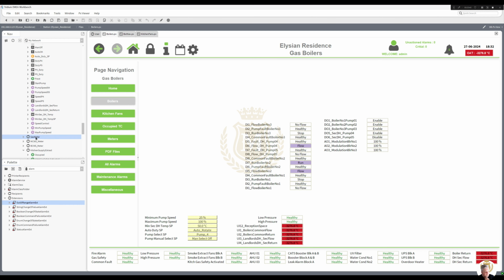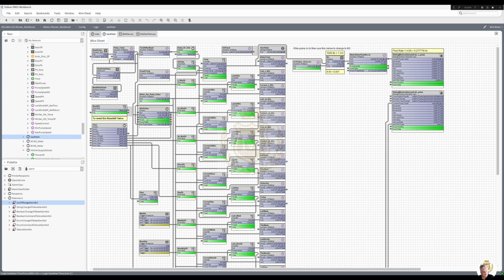What else? Oh, gas meters and MCWS and BCWS. Same folder, same logic in there. You might have seen this before on previous jobs. I have a standard folder that I have with all my bits and pieces in. And we're basically just adding up. So I've improved it since the last time. I've put the meter pulse value in. At the moment I always had it as a 1, but now I've made it adjustable. Now it probably is a 1, I don't know until I get to site, or it may be 0.10 per pulse, but they differ. So at the moment it's 0.01, which is sometimes standard on most sites, but there again it could prove me wrong, and it could be a 1 meter cubed is 1 pulse. I don't know until I get to site, but I've got the option now of adjusting it, which then adjusts it all the way down for all the histories.